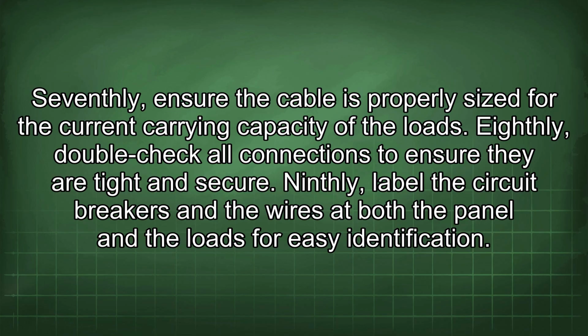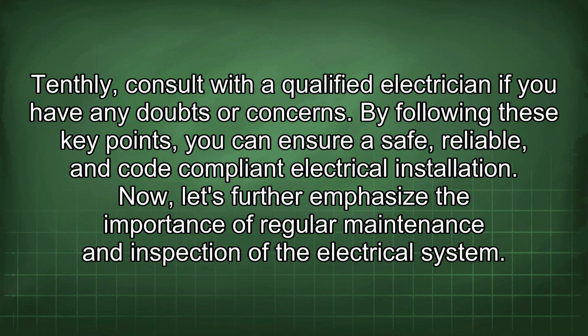Seventhly, ensure the cable is properly sized for the current carrying capacity of the loads. Eighthly, double-check all connections to ensure they are tight and secure. Ninthly, label the circuit breakers and the wires at both the panel and the loads for easy identification. Tenthly, consult with a qualified electrician if you have any doubts or concerns. By following these key points, you can ensure a safe, reliable, and code-compliant electrical installation.